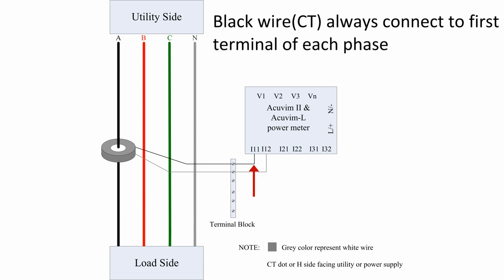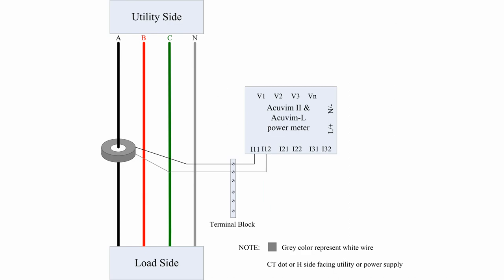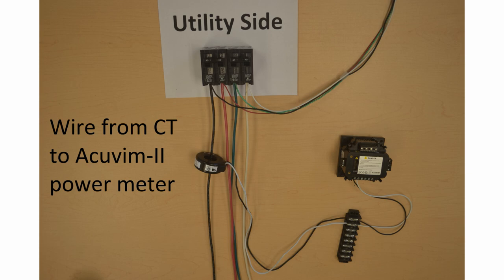The black wire is always connected to the first terminal of each phase, in this case I11. The white wire is then connected to I12. Here we are demonstrating the connection from the CT to the meter via the terminal block. The wire connection is being made in the order of black, then white.